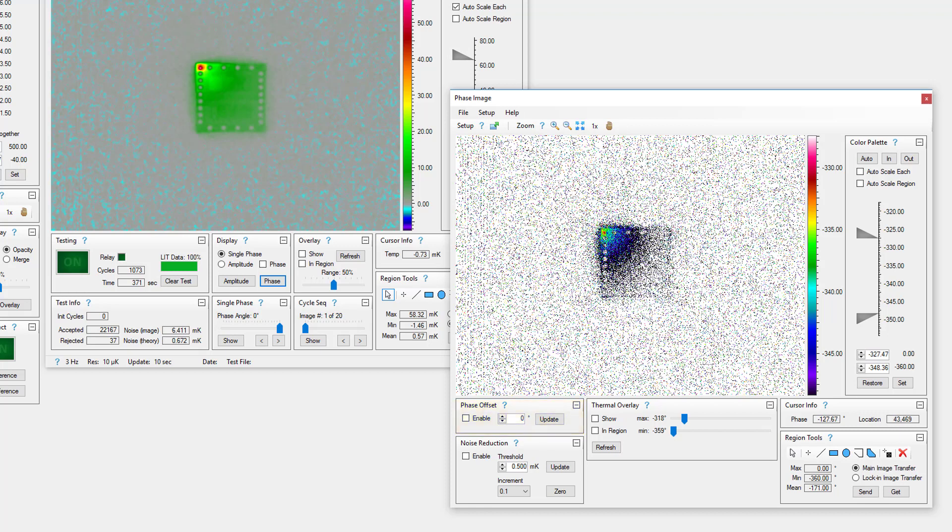The phase image is created by calculating the inverse tangent of the single phase image at negative 90 degrees divided by the single phase image at zero degrees. If pixel values in these single phase images are below the noise reduction threshold, the resulting calculated phase angle will be noisy and unreliable. Noise reduction zeros noisy pixel values by setting them equal to negative 360 degrees.